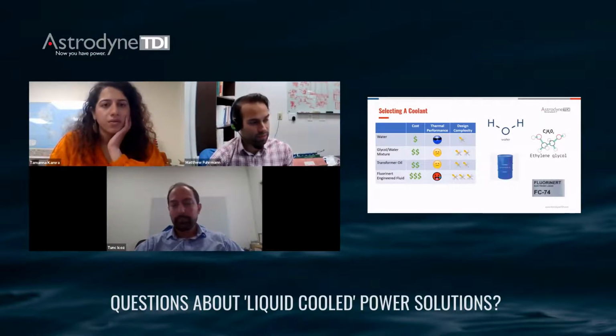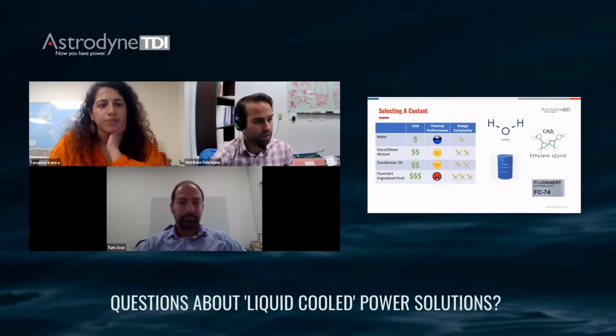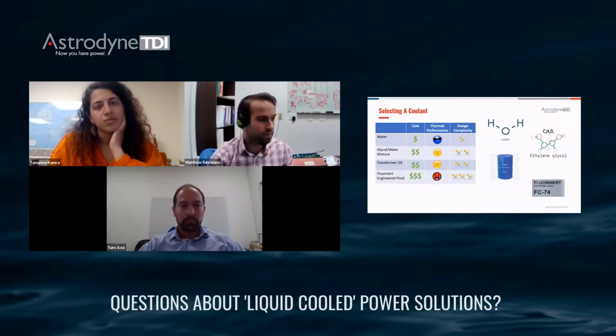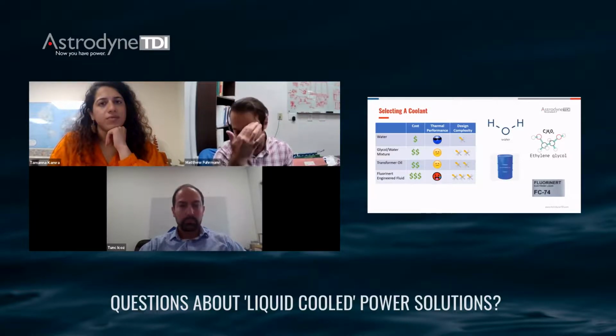And just as an example, in terms of the design complexity for the Fluorinert, the reason we have the 3 tool symbols signifies the high complexity to design around, is that when you're selecting the fluid like the Fluorinert, the Fluorinert molecule is very, very small, so it's subject to leaking. So you have to take special considerations, and also a coolant such as that will extract elastomers from any gasket seals that you might have in your design. So you have to make sure that the material selection takes this into consideration, because there are gasket materials that will not be something you can't use with a Fluorinert.